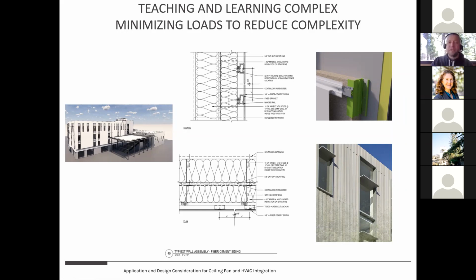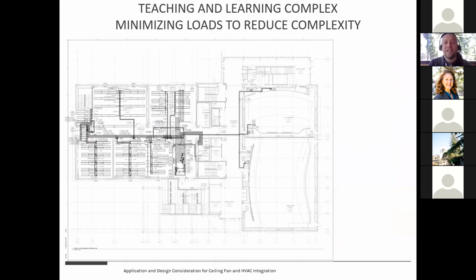A very thick assembly, lots of insulation, good rain screen design, and really good solar control—all of these work together to reduce how much of the ceiling needs to be covered with radiant panels. It's not often in this class that we show mechanical drawings, but here you can see each of the radiant panels laid out with the piping that goes to each one. The key thing is radiant ceiling panels are not inexpensive.